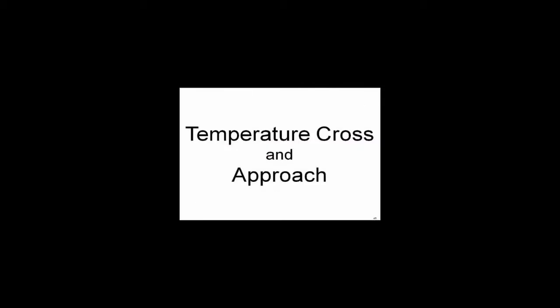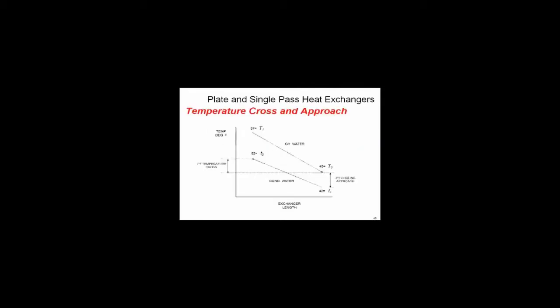So what does that mean in temperature cross and approach? Let's take a quick look and try to educate everybody real simple, not trying to make heat transfer experts out of you. But if you're going to do water-side economizers, you need to grasp some of this because you have to pipe them accordingly. You put them in, you've got to pipe your plates or your straight tube heat exchangers accordingly. So what does the temperature cross? What does it mean for a plate or single pass heat exchanger? What is approach? What does it mean? Look, I'm working a cooling tower. I'm trying to make 52-degree water out of 49-degree wet bulb. I'm trying to give you 49-degree cooling tower water to the heat exchanger to give you 52-degree water on the chill water side. I'm trying to get a tight approach. That would be a three-degree approach. So the message is I want to make as cold water as I possibly can on my water-side economizer. And the limitation of that is how cold a water can I make my cooling tower? How cold a water can my cooling tower give me? And how close to that cooling tower temperature can I make water? Can I make chill water using a heat exchanger of some kind? How close? That's the approach.